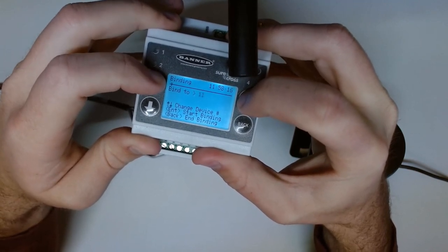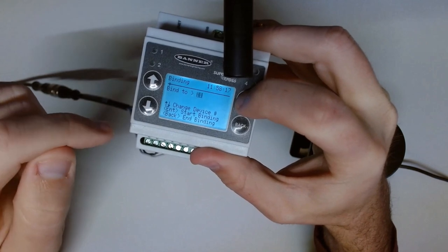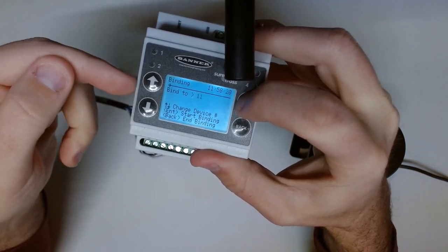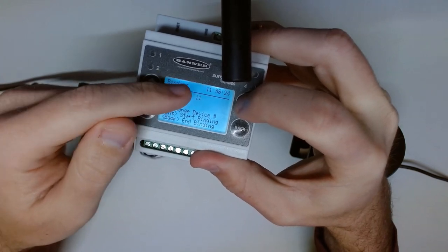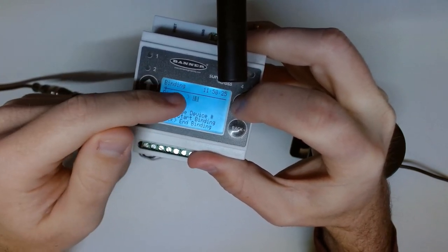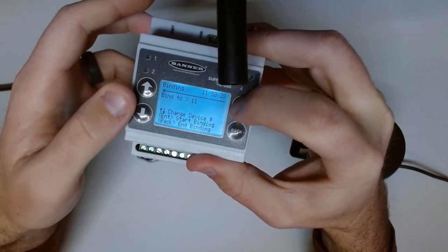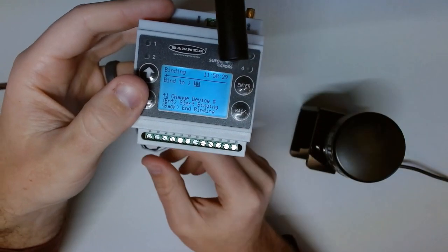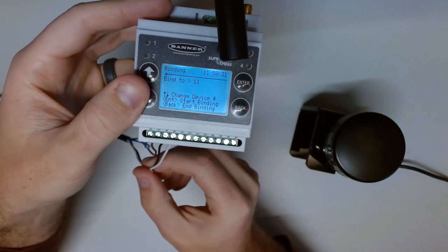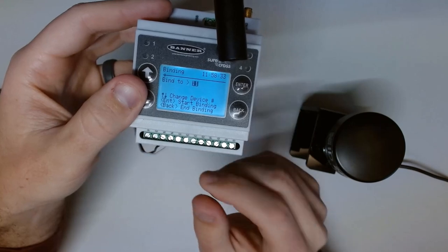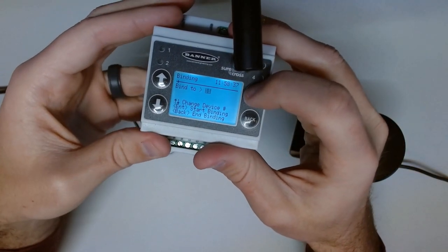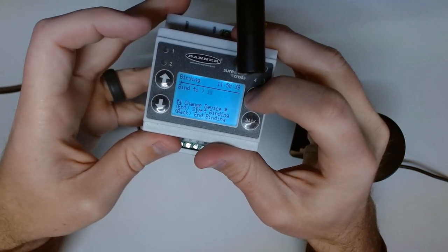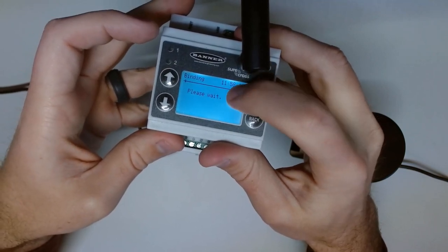If we want to actually do the site survey through the screen, we need to bind it to a specific ID, and that ID needs to be 11 or higher. The 2 through 10 are for locally wired devices. 11 and up are for any wireless devices. So, I'm going to go ahead, and I'm going to bind this to start the binding at 11.